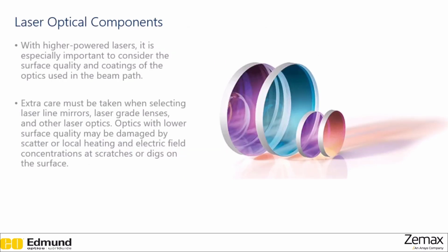Laser optical components need to be chosen with care for laser systems. Especially with higher powered lasers, it's especially important to consider the surface quality and coatings of the optics used in the beam path. Poor surface quality can lead to heating and damaging of the optical element, as well as scattering from the defect on the surface, damaging the coherence of the laser beam.